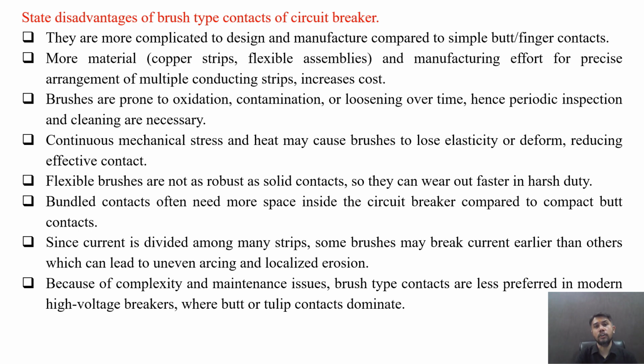Disadvantages of brush type contacts of circuit breaker. They are more complicated to design and manufacture compared to the simple butt or finger type contacts. They require more material, copper strips, flexible assembly and manufacturing effort for precise arrangement of multiple conducting strips. Hence, the cost is increased.